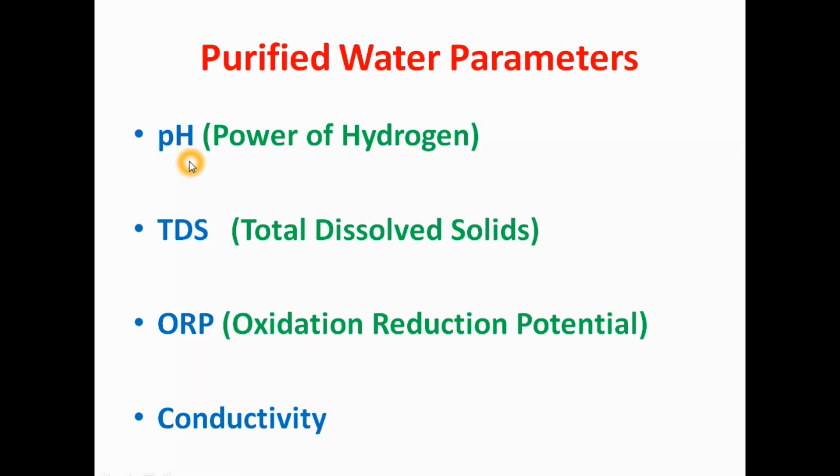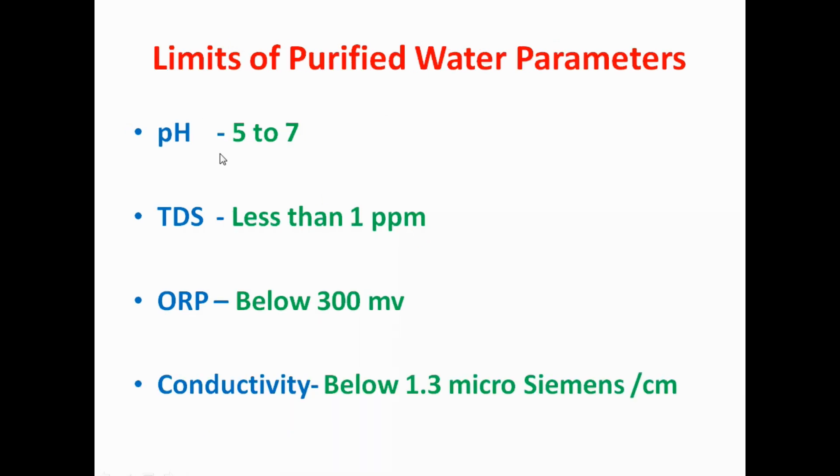Now we will see the range or limit of all these parameters. pH should be 5 to 7. TDS should be less than 1 ppm. ORP should be below 300 millivolt. And conductivity should be less than 1.3 microsiemens per centimeter. These are the parameters and their limits.